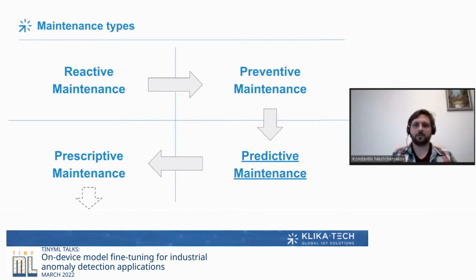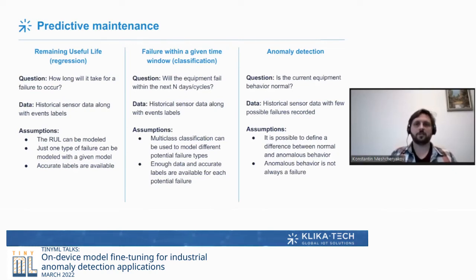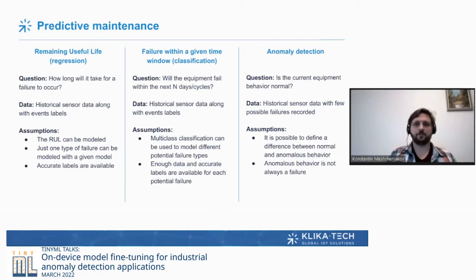We're focusing on predictive maintenance as something that can be implemented right now. There are several approaches. First, we can predict the remaining useful life of a component — how long before a failure occurs. To create such a model, you need historical sensor data along with event labels. When a device breaks, a serviceman should add an entry to a database to act as a label. This is not simple to collect — you need to deploy a fleet with sensors and let it operate for significant time, since failure events are quite rare.